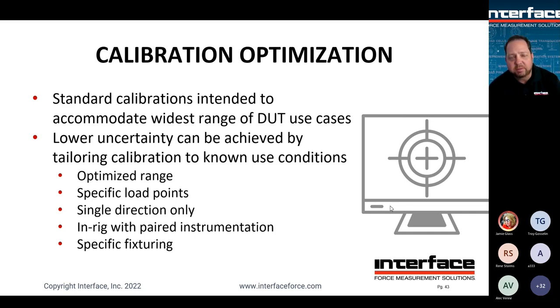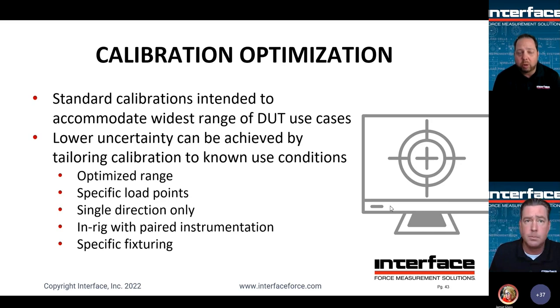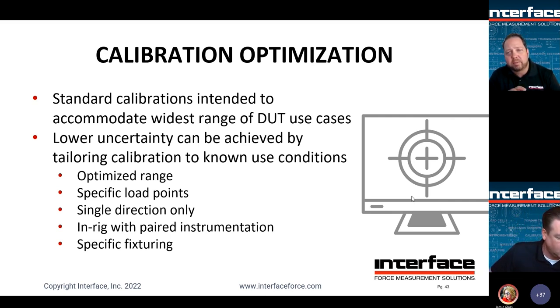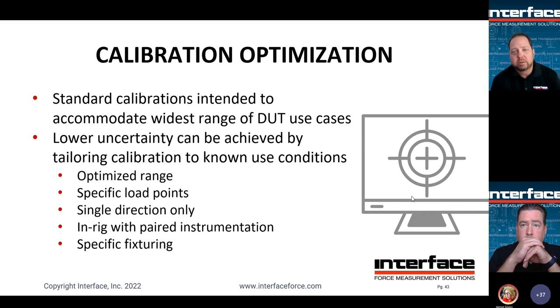So the other thing to think about is specific fixturing. We put a lot of effort and design into our sensors so that with proper installation, of course, fixturing is the least amount of error source as possible during actual test. But the reality is some sensors, such as load pins, for example, can be quite a bit more sensitive. So oftentimes, if we're trying to achieve maximum precision, lowest uncertainty, we'll actually perform calibrations in fixturing that we know are going to be used in the actual test, right? So for example, for a load pin, we might do something that is representative or that is the actual test clevises or test shackle arrangement. So things to think about. There's a lot of ways that we can custom tailor, or you can custom tailor a calibration you're performing to better fit known use conditions, okay?